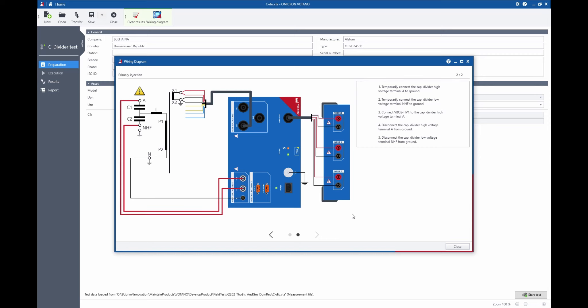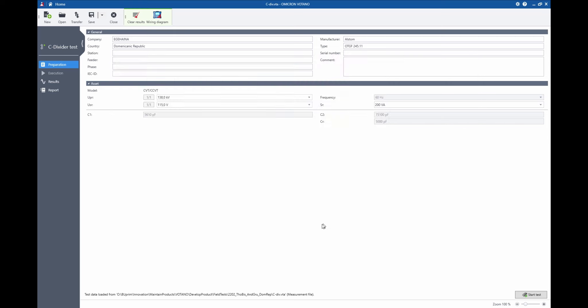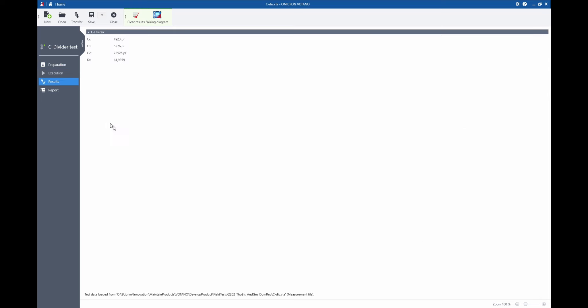After this measurement we add a cable to the upper part of the stack, and once those two frequency sweeps are done our measurement is complete. We can see the results which will look something like this, and we see that we have individual results for C1 and C2, but also a result for the overall capacitance and for the capacitive ratio.